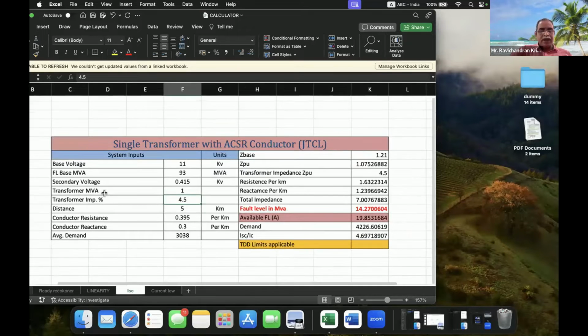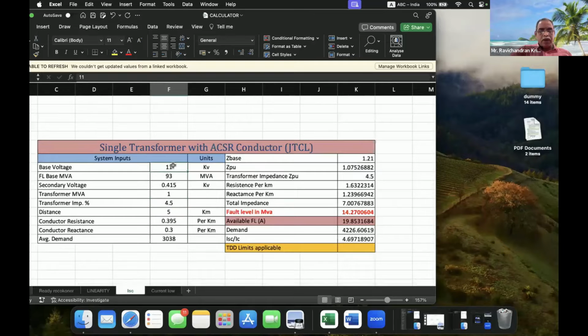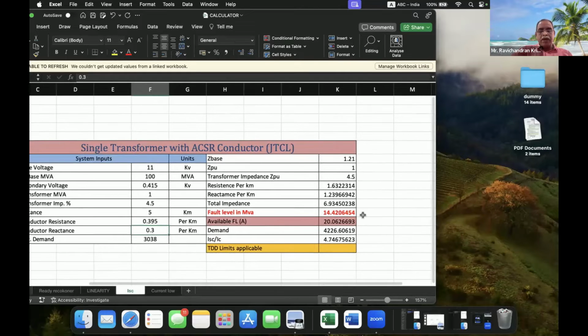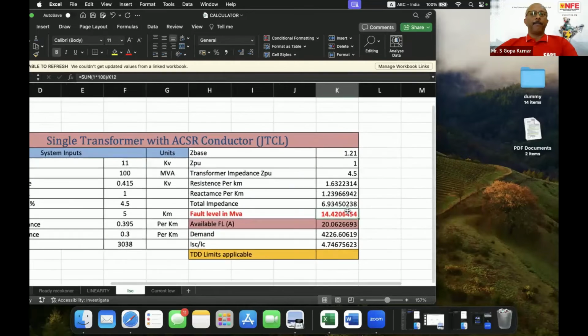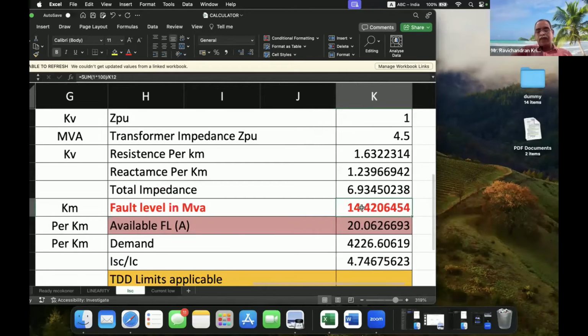So here, let us see that. For example, I am having an 11 kV system, and I am just putting in fault level values. For example, 100 MVA here, and 415 volt secondary, and the transformer is a 1 MVA transformer. Impedance I have just given as 4.5%. The distance of the ACSR conductor is 5 kilometers, and I added the conductor resistance and reactance of the ACSR conductor here. I got the fault level here, 14.42 MVA.